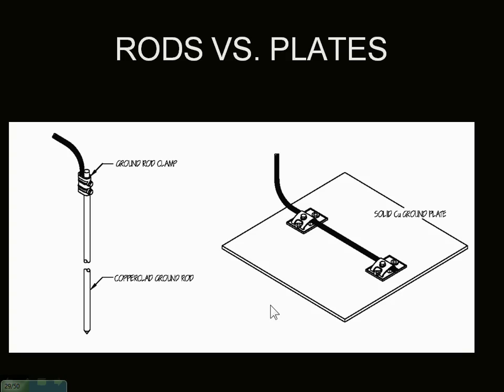Is there a value you can look for, like overall for a system - resistance? Surprisingly there isn't any concrete number you have to adhere to. A lot of owners want it to be under 5 ohms, and that's just personal preference. Our system really has no requirement - as long as you get your ground rods in every 10 feet, it's good enough. But yeah, a lot of owners want it under 5. Some want half an ohm or less, which is pretty rare and kind of hard to achieve.